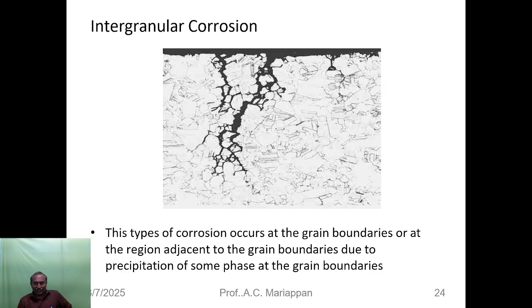This can be joined by intergranular mechanisms, called hydrogen induced cracking, simply called HIC. If stress acts on the material - such as vibration - equipment is usually classified as static or rotating. Static equipment has no external stress acting on it. But rotating equipment, like a pump or turbine, has external stress acting along with corrosion - that is stress corrosion cracking, where stress is one of the factors involved along with corrosion, called SCC.